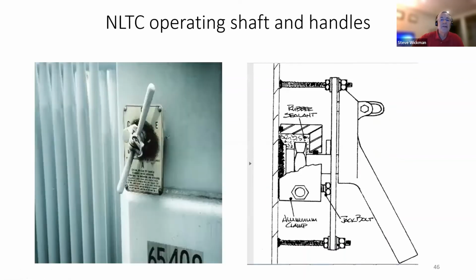On that one, no load tap operating shaft and handles. Where that operating rod penetrates into the transformer tank, there's a bushing of some sort with a flange that can develop leaks. And in this case here, we were able to take advantage of that faceplate and build a little clamp to put behind that faceplate, use a jack bolt to push it up into place, fill that with sealant compound, and effectively contain the leak on that.